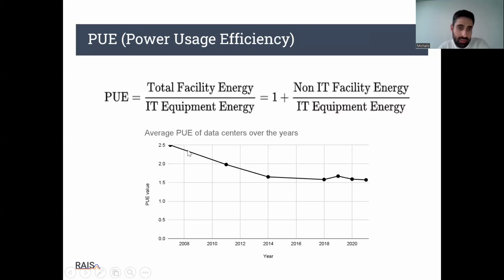Power usage efficiency is a metric used to evaluate the efficiency of a data center, representing the proportion of power spent on IT equipment relative to non-IT equipment. The lower the value, the more power efficient the data center. On this diagram, you can see the average PUE of all data centers globally over the years, showing significant improvement since 2007, from around 2.5 down to about 1.5 nowadays.